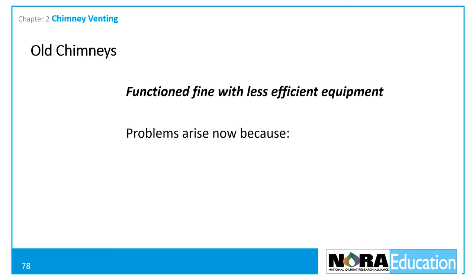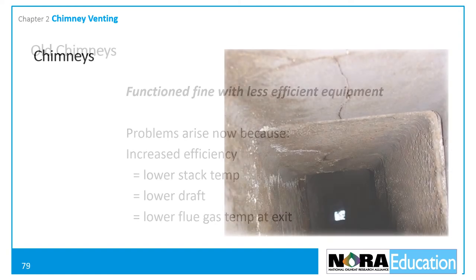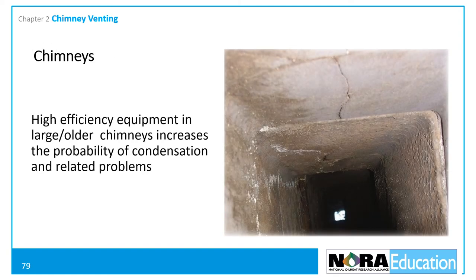All of these improvements have led to problems with chimneys that had functioned properly with older, less efficient oil heat equipment. Exhaust temperatures decrease as efficiency increases, and chimney draft decreases as flue gas temperatures drop. In addition, flue gas temperatures at the top of the chimney decrease as the gross stack temperature drops. Installing higher-efficiency equipment in larger or older chimneys increases the possibility of flue gas condensation and related chimney concerns.